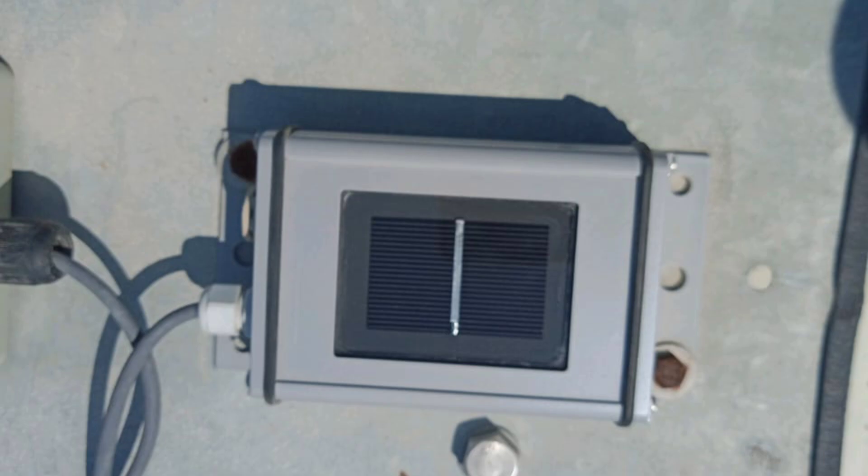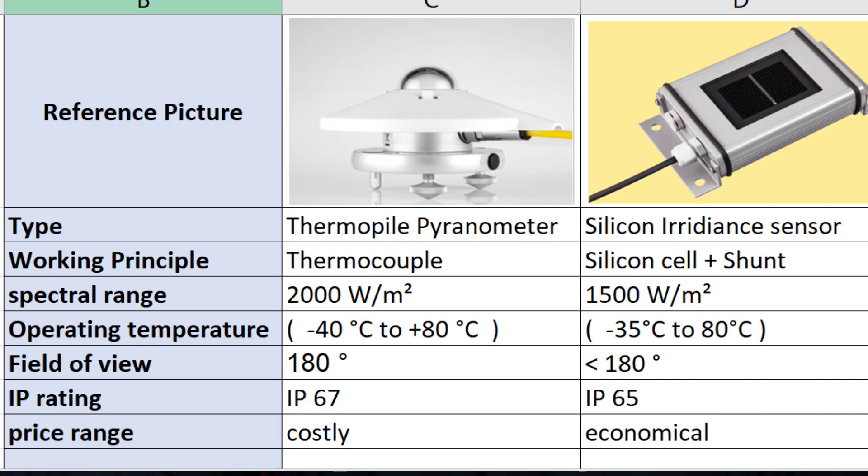In the case of the silicon-based irradiation sensor, you get a monocrystalline single solid cell connected in series with a shunt resistance using silicon photovoltaic technology. Whenever a light photon falls on it, electrical current is generated directly on a milliamp scale. We then integrate this with our SCADA system — for a certain amount of milliamp current, you get a certain amount of radiation, just like a CT ratio on a digital platform.